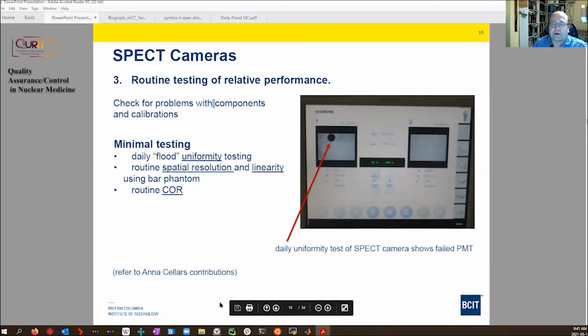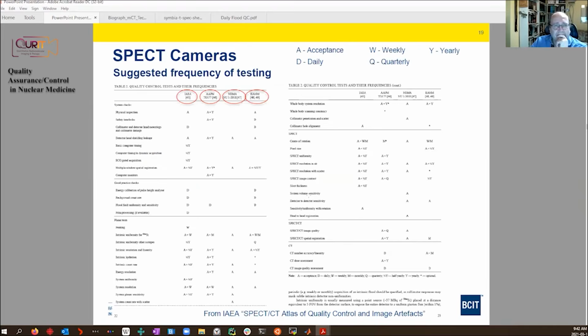I just want to give you one result of the testing. I think this was probably 10 or 15 years ago, on a camera at Children's Hospital. This was a dual head SPECT camera. If you look at detector 2 on the right, that doesn't look so bad. If you look at detector 1, oh my goodness, what's that? Here there's a big dark area of zero count density. This is indicative of a failure of a photomultiplier tube. If this testing wasn't done and patients were scanned with this camera, the images would be of very poor diagnostic quality. As a matter of fact, they could cause harmful, incorrect diagnoses.